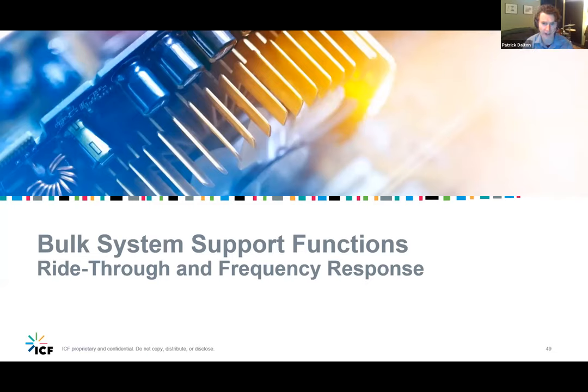It's heating up the line, which is reducing the thermal capacity, or just the ability to transfer useful power, essentially. And so that interaction, if that were to occur, would be undesirable. We would want a regulator to still be able to move and really regulate the feeder voltage. And then I'm seeing the DER volt var function is more trying to mitigate its own impact on the grid and not necessarily try to move the entire grid voltage. So that is one type of interaction that we do need to watch out for.